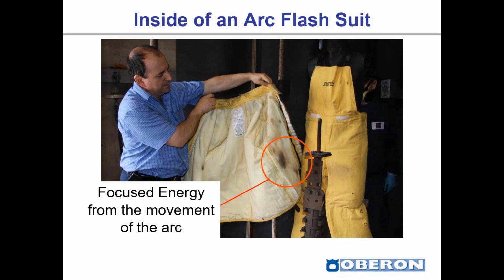This image here from the test laboratory just shows an Oberon coat and bib overall. Again, that arc is rather unpredictable. So the arc does track, it does move. We show that image where I'm circling that one spot where we had focused energy from the movement of the arc. Thankfully, the design of the arc flash suit often is a bib overall with a coat, and then you have your suit hood. So there is sufficient overlap. So the corresponding area behind that darkened spot on the coat, on the bib overalls, doesn't show much damage. Therefore, the worker would not have seen enough heat. We shouldn't have had any injury whatsoever.